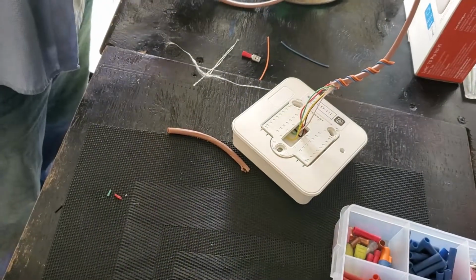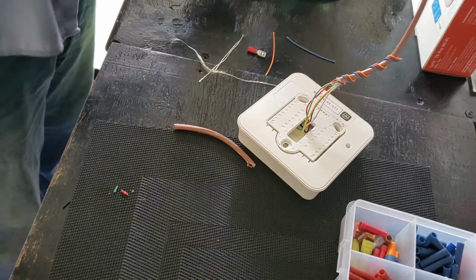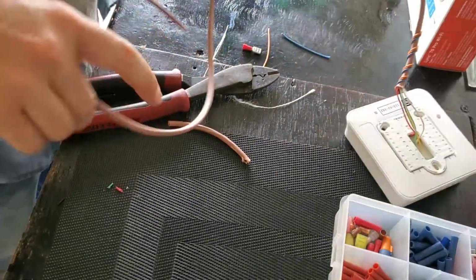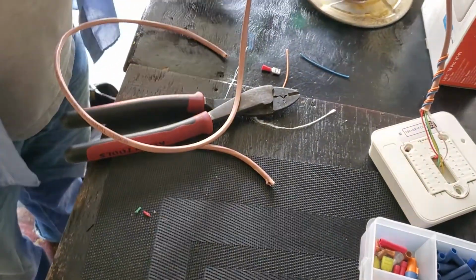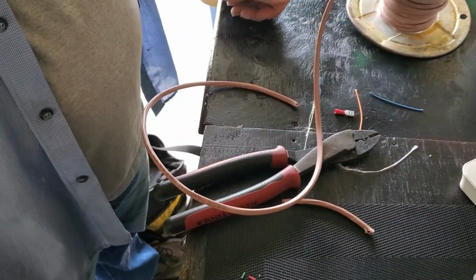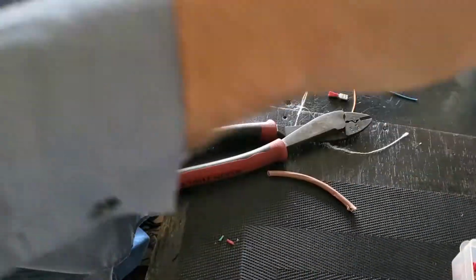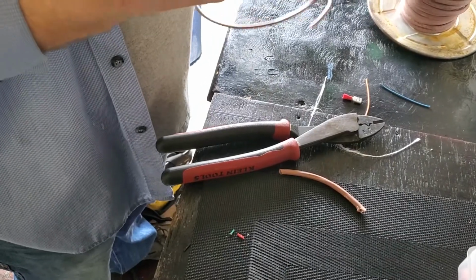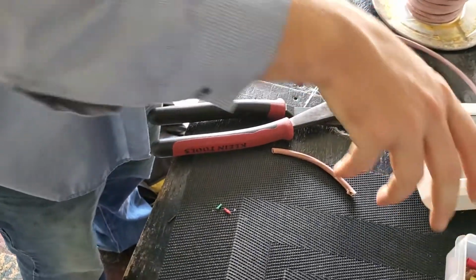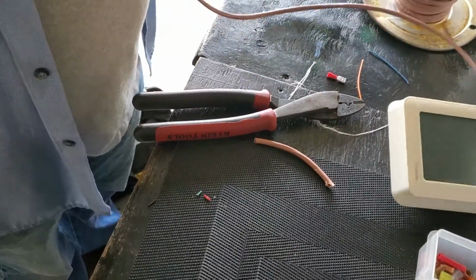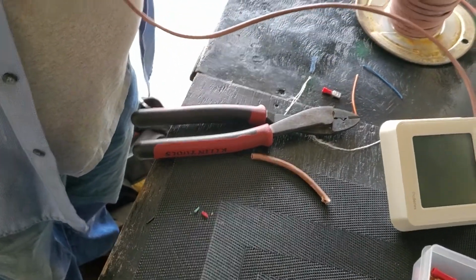You mean the condenser? Yeah, well, the condenser and the air handler—you've got contactors in both. You've got a contactor in your condenser that's controlling your compressor and your condenser fan. And then you've got contactors in your air handler that are controlling your blower and your heating stages if you've got electric heat.